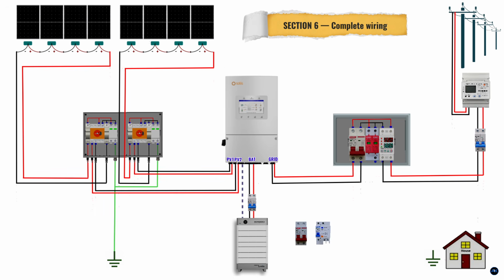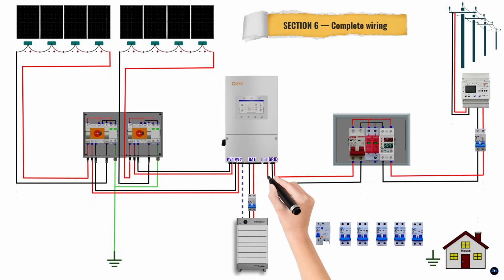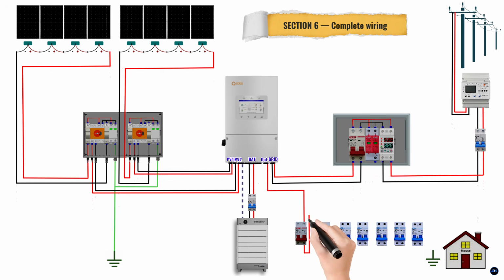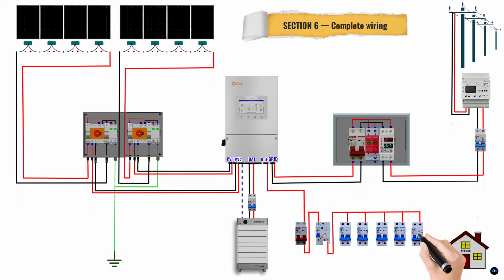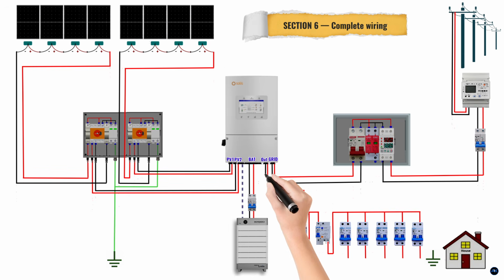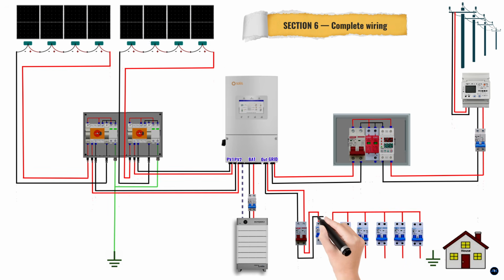Step 4. Output to load board. The inverter's 6 kilowatt AC output feeds your distribution board through 10 millimeter squared cable, again under 3 meters. Inside the board, the 40 amp incoming MCB first, then the RCD, 40 amps, 30 milliamps. Every load circuit passes through this device. It is the one that stops electrocution, non-negotiable. Then 5 individual circuit breakers, lighting at 10 amps, power sockets at 16, kitchen at 20, air conditioning sized to its load, and a dedicated critical backup circuit. Label every single breaker.